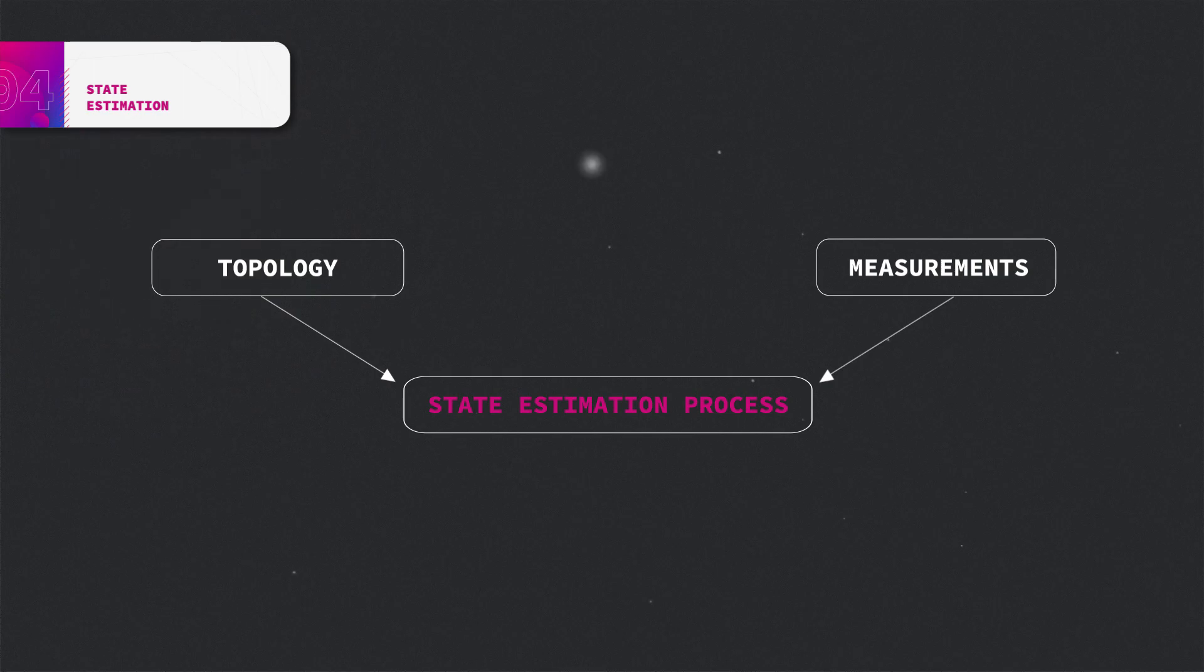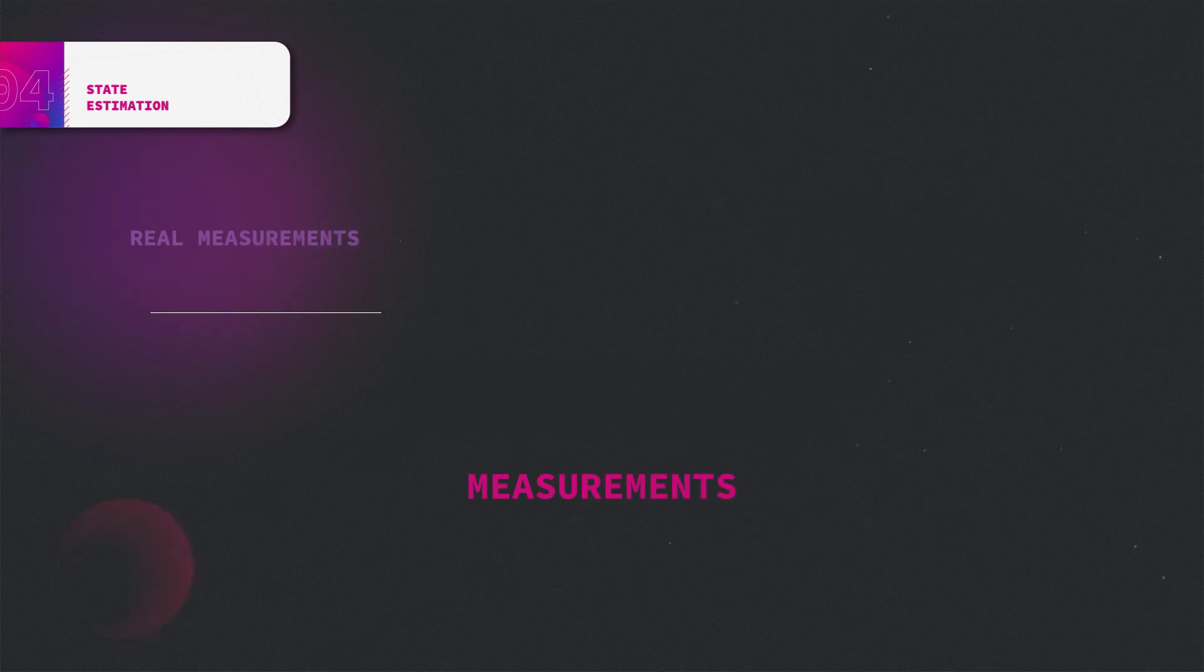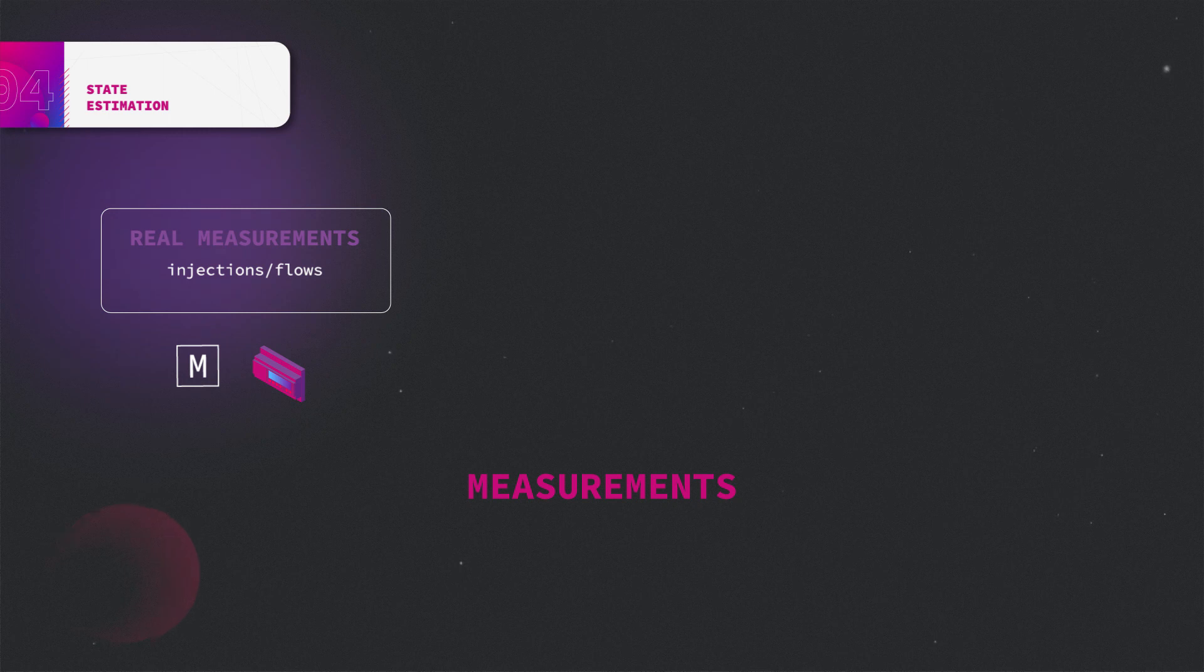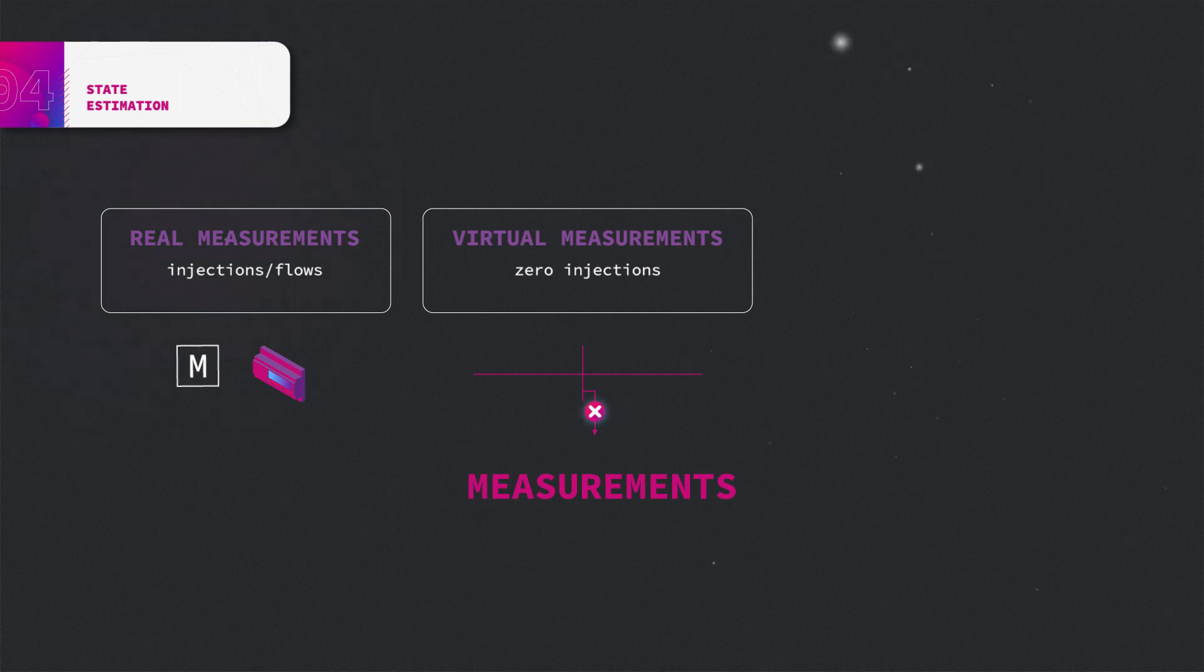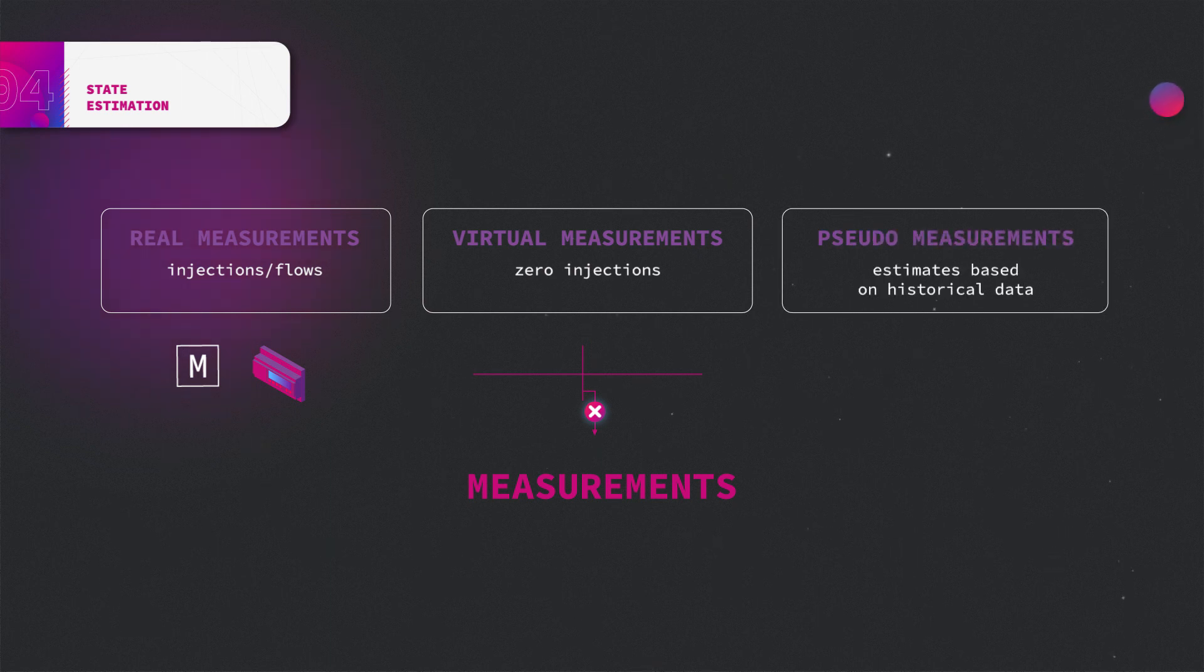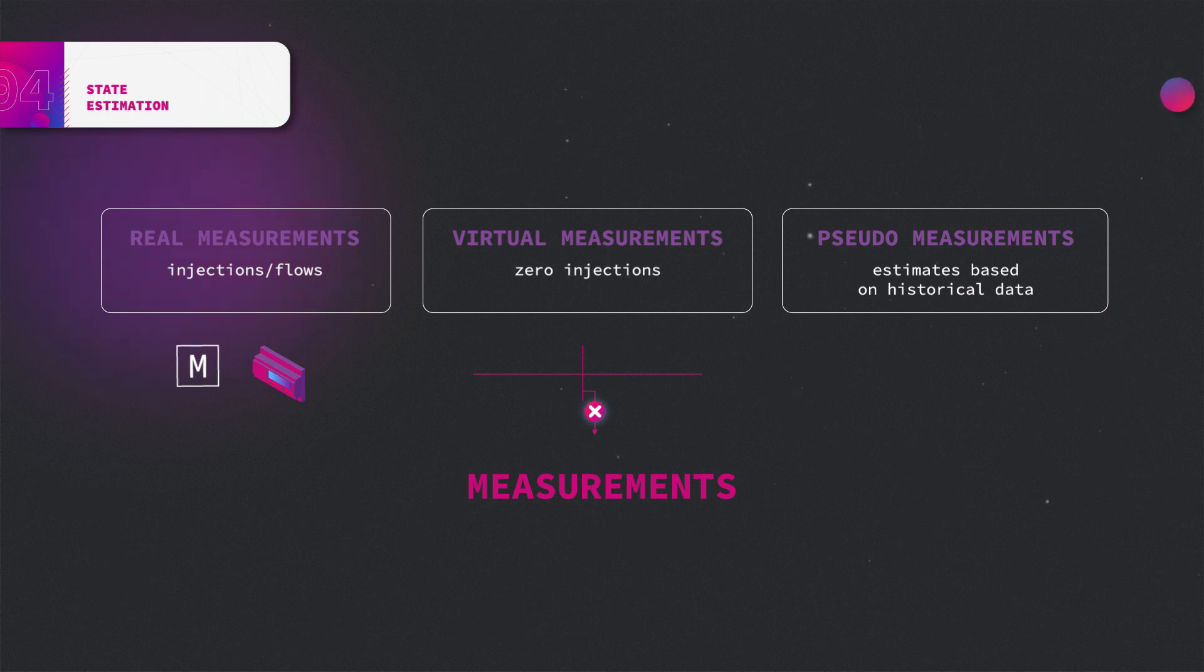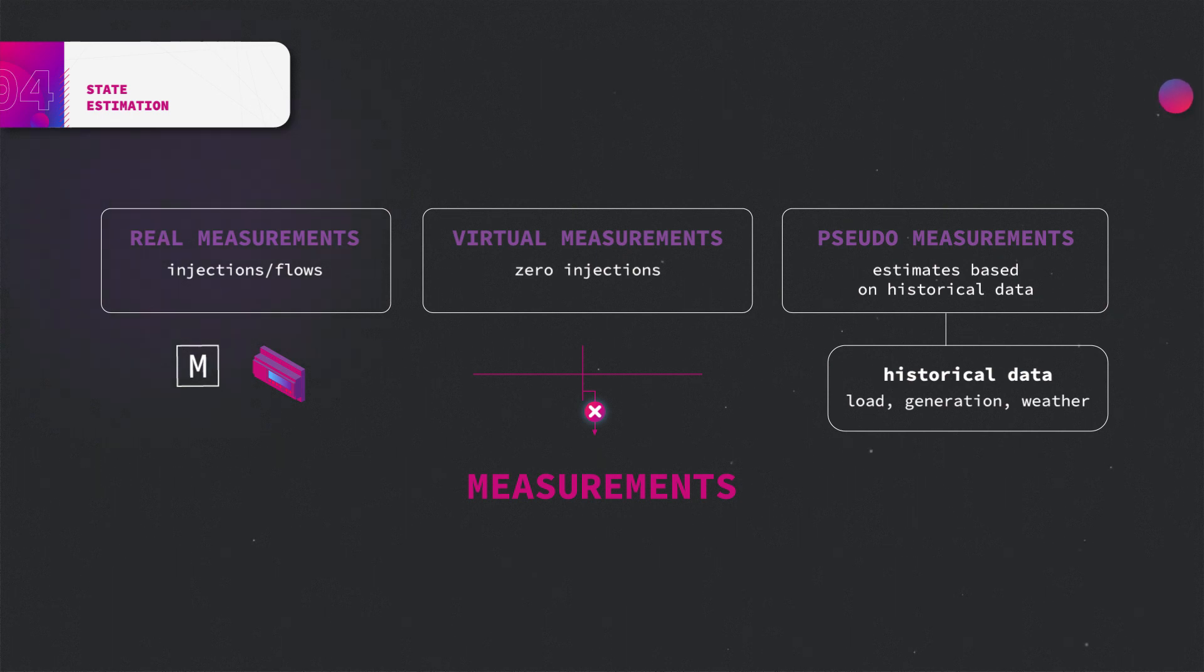Measurements consist of real measurements, which are actual measurements from the meters in the network acquired in real time, virtual measurements, which are measurements on the buses without any load. If there is no load then loading in this bus can be fixed to zero in advance. Pseudo measurements that are estimates based on historical data and advanced algorithm. These are calculated for the locations where there is no meter present or the existing meter is in an error state.